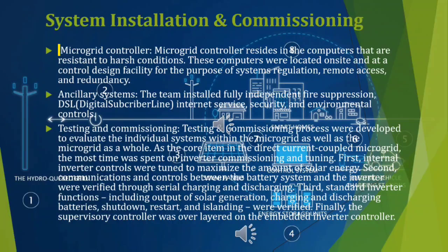Microgrid controller. The microgrid controller resides in computers that are resistant to harsh conditions. These computers were located on site and at the control design facility for the purpose of system regulation, remote access and redundancy. Testing and commissioning. The testing and commissioning process was developed to evaluate individual systems within the microgrid as well as the microgrid as a whole. The microgrid is a direct current coupled microgrid. The most time was spent on inverter commissioning and tuning.